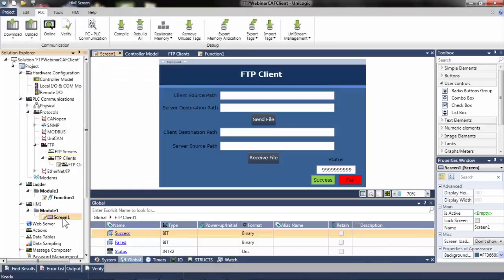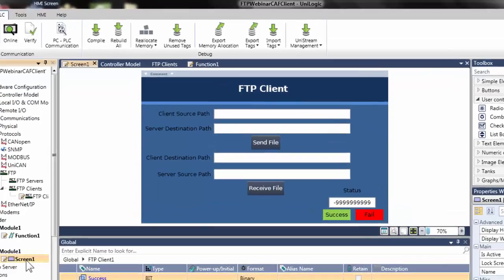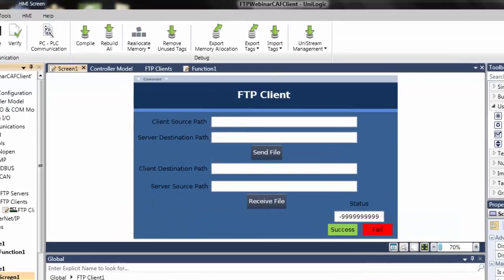An HMI display screen has been previously built in this video. The client source path, server destination path, server source path, and client destination path have been previously linked to four separate user-defined text boxes on the HMI. These tags are used to reference file locations on the SD card and server. The send file and receive file buttons will trigger the transfer of files. On the bottom right-hand corner of the HMI display, the status message, success bit, and fail bit are used to monitor the progress during the transfer.